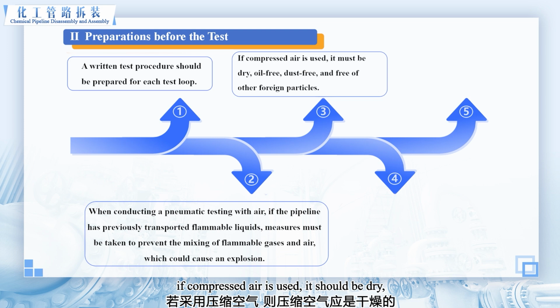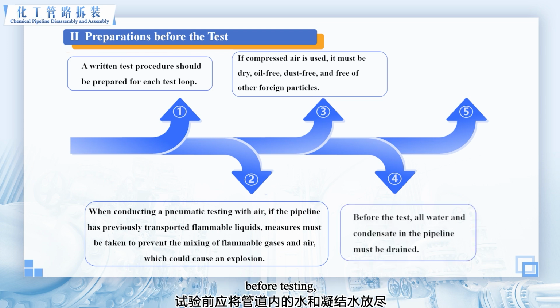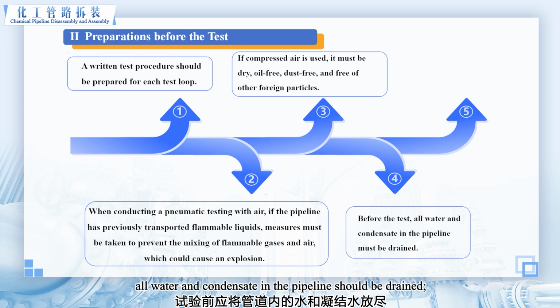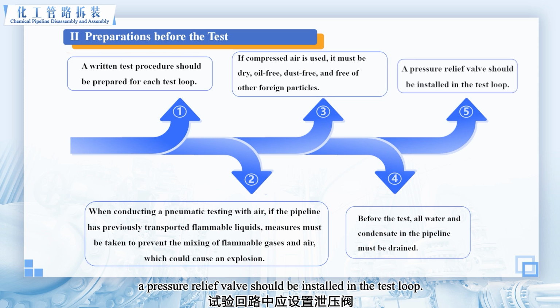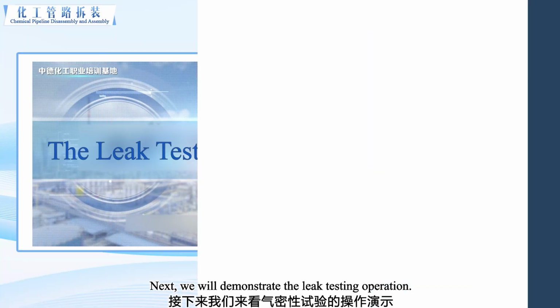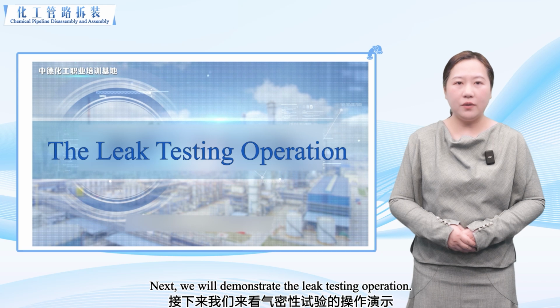It should be dry, oil-free, dust-free, and free of other foreign particles. Before testing, all water and condensate in the pipeline should be drained. A pressure relief valve should be installed in the test loop. Next, we will demonstrate the leak testing operation.